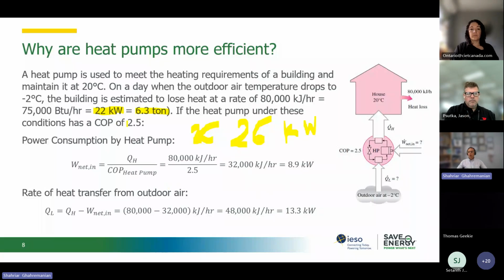Let's assume that we have a heat pump whose COP, or coefficient of performance, is 2.5. This means that we only need to install a 9 kilowatt heat pump for this building, and that would be enough. So this is great. A 9 kilowatt heat pump can provide the same 22 kilowatts the building needs, versus the natural gas, which was 26 kilowatts, or a resistance heater, which is going to be 22 kilowatts. This is the reason the heat pump is more efficient to use inside our building.